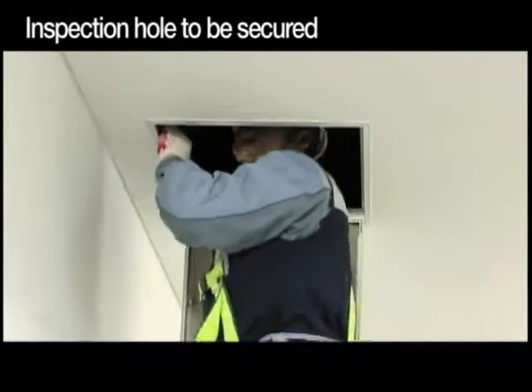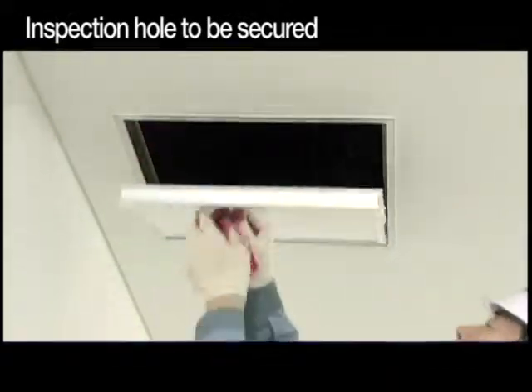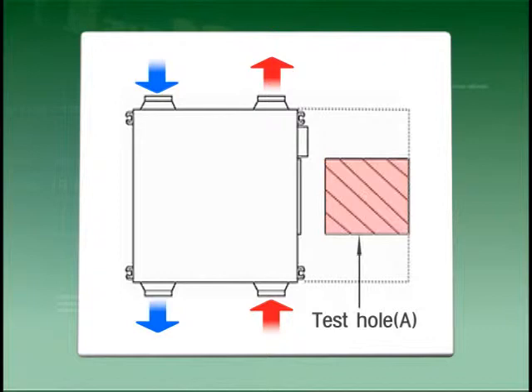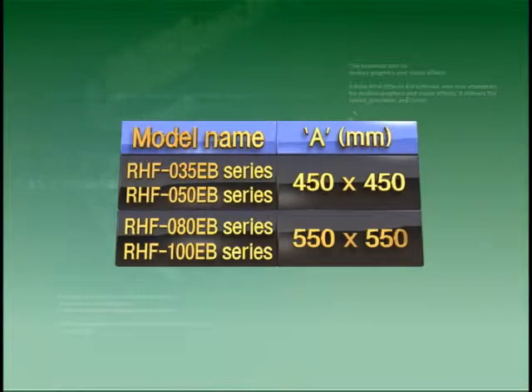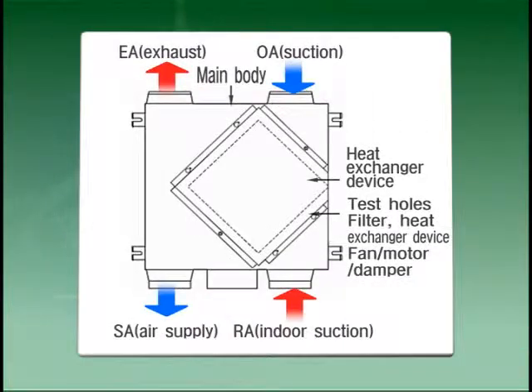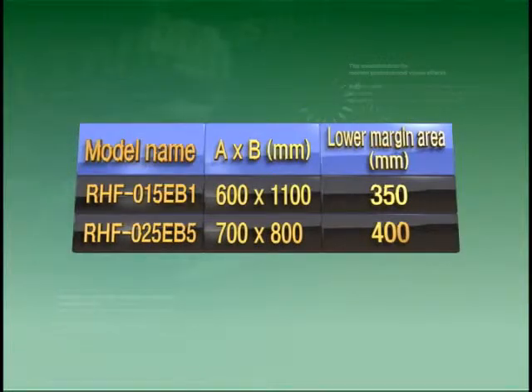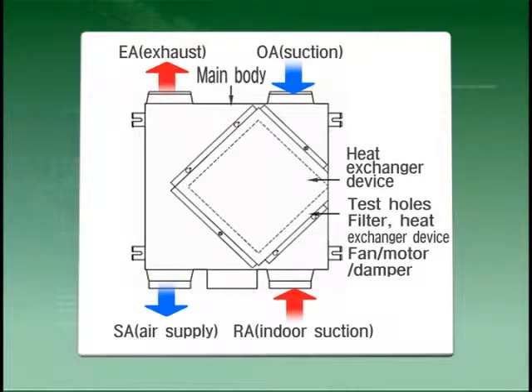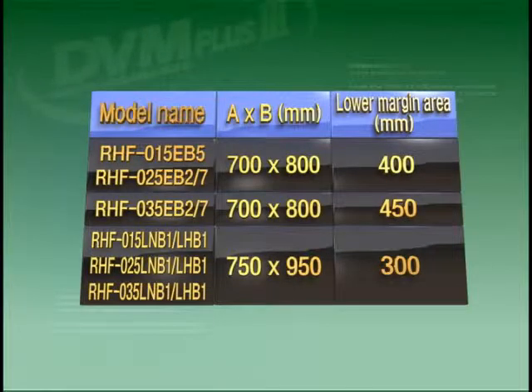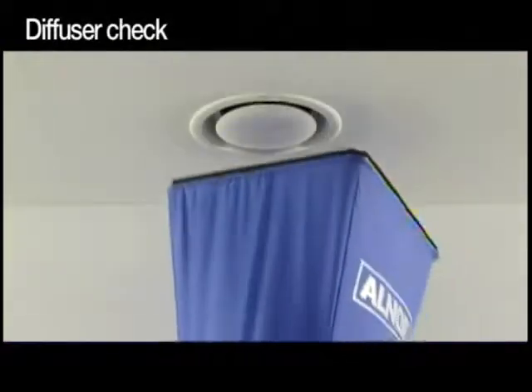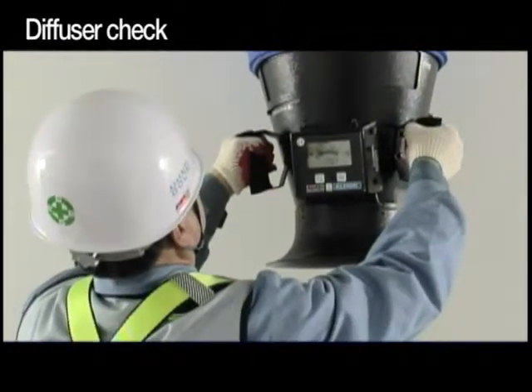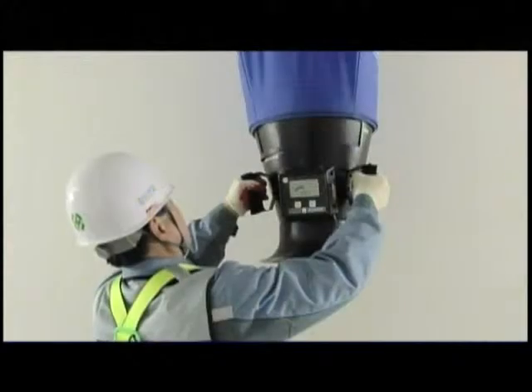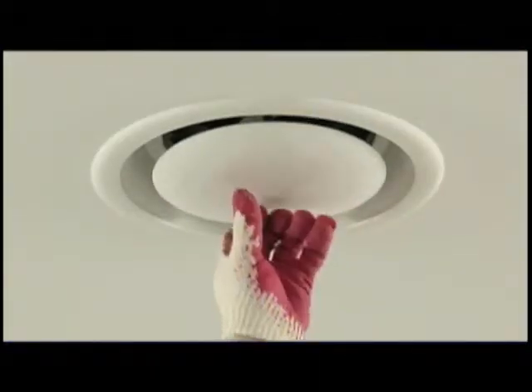Finally, install an inspection hole for repair and maintenance of your product. The following size of inspection hole for each equipment is used. After measuring the amount of wind from your diffuser, adjust the diffuser until the amount of wind is evenly distributed. Check if there are any abnormal noises from the equipment and the diffuser and check that the equipment operates properly.